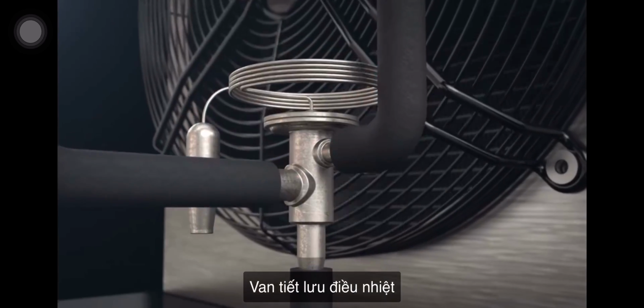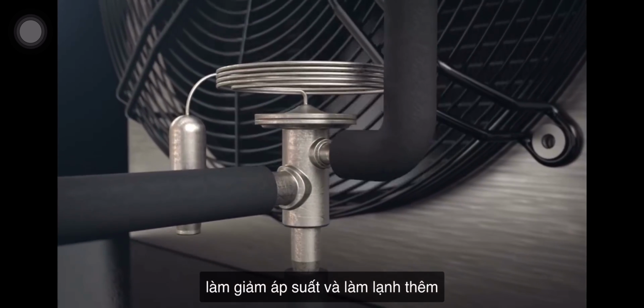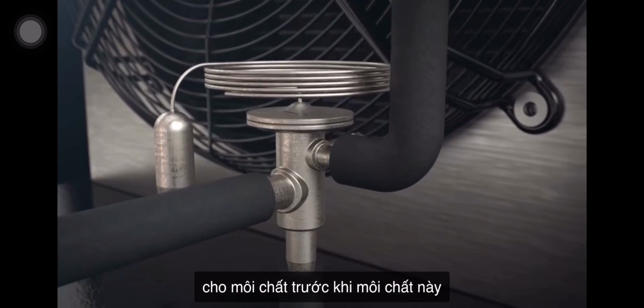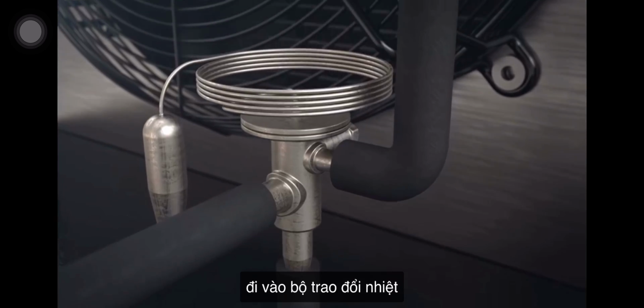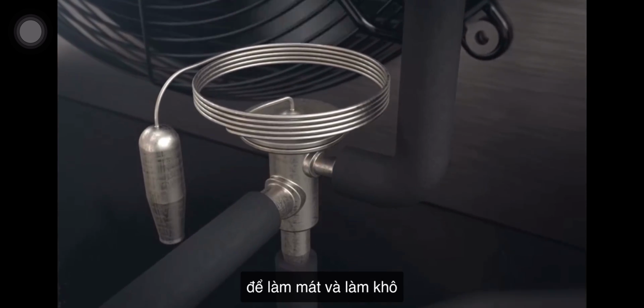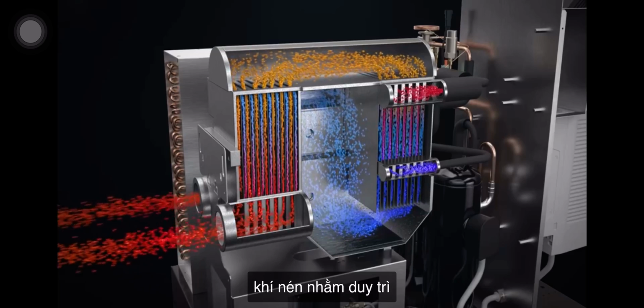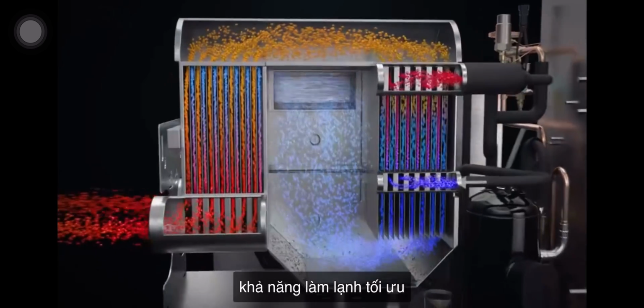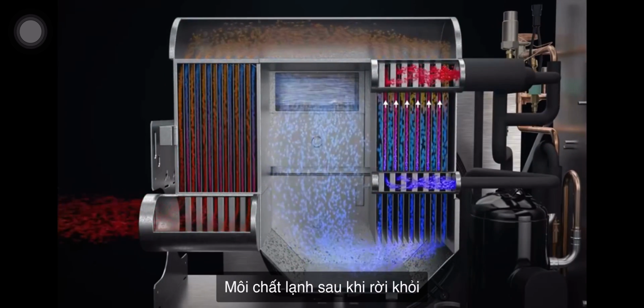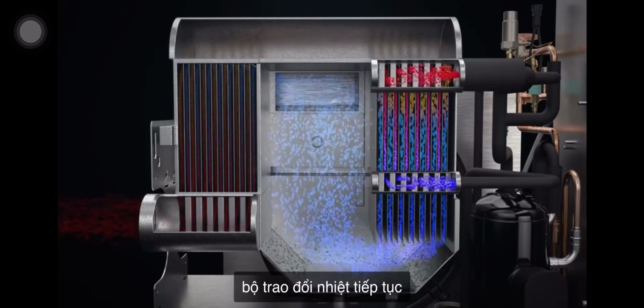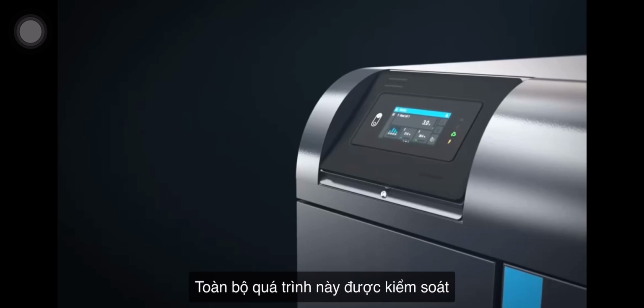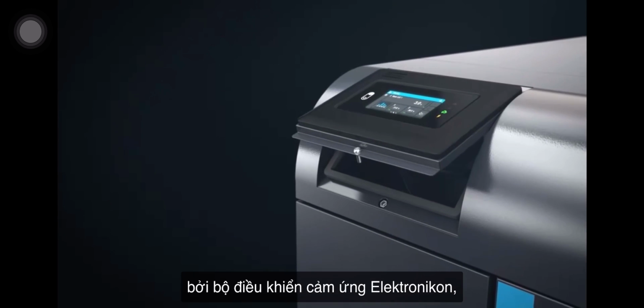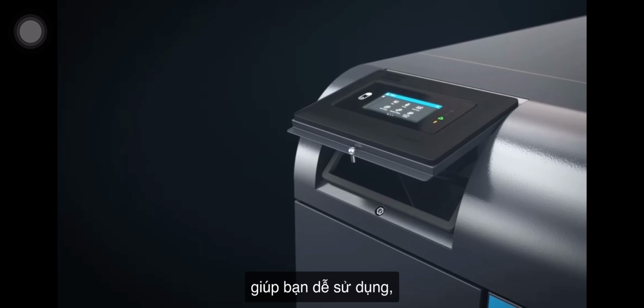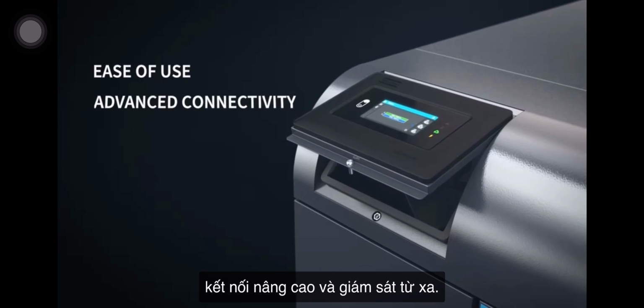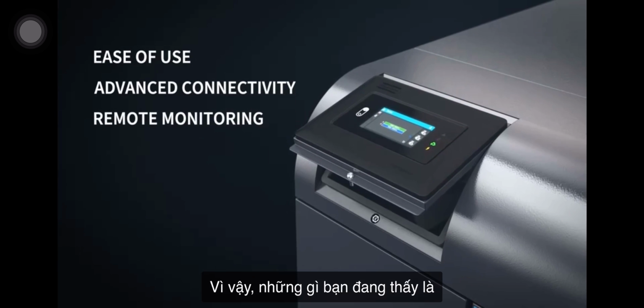The thermostatic expansion valve reduces the pressure and cools the refrigerant further before the refrigerant enters the air-to-refrigerant heat exchanger to cool and dry the compressed air. To maintain optimal cooling capacity, the refrigerant then leaves the heat exchanger again to continue the refrigeration generation loop. This entire process is controlled by the Elektronikon Touch, which gives you ease of use, advanced connectivity, and remote monitoring.